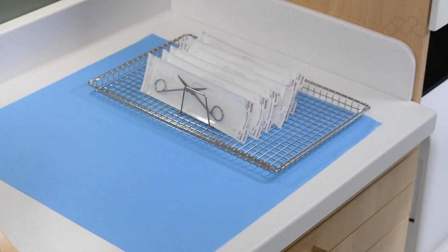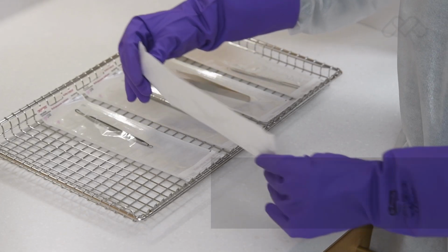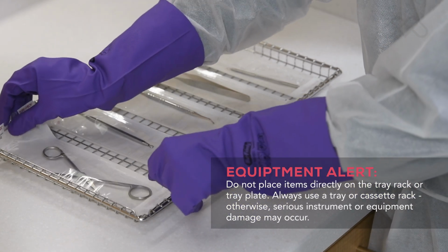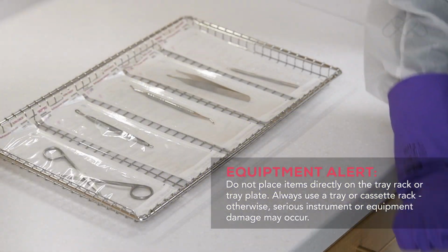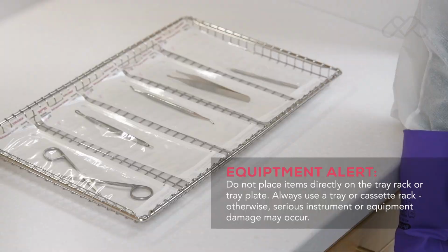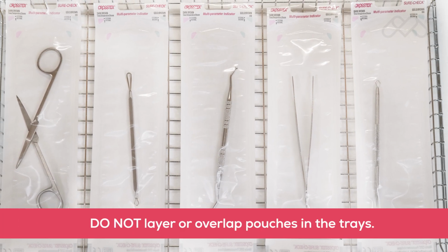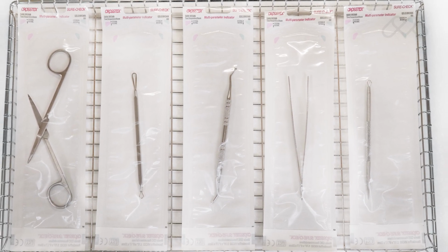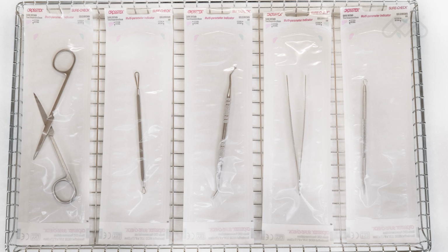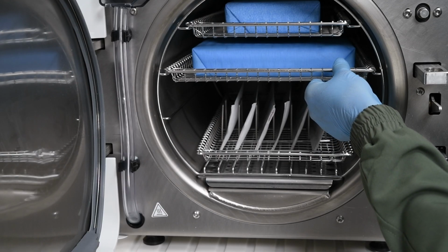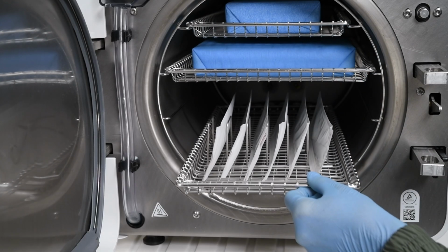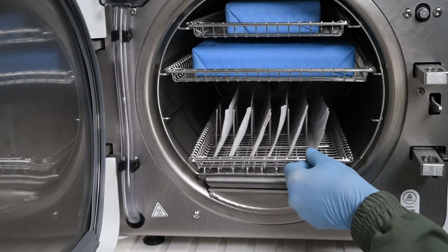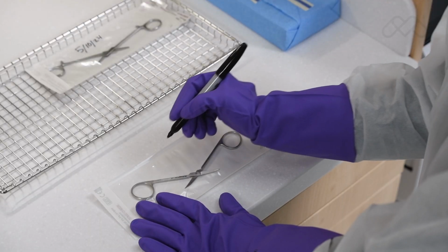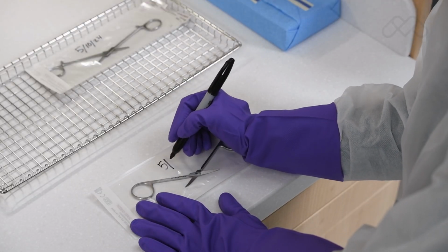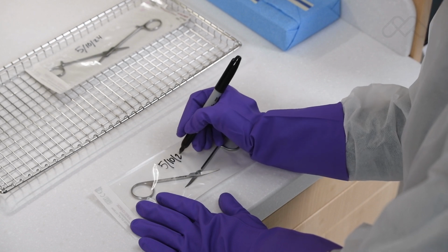Proper loading is using a pouch rack. Without a pouch rack, pouches loaded directly on the trays will dry best if loaded with the paper side down. Do not layer or overlap pouches in the trays. Pouches should be loosely packed with the handpieces and instruments, single height loaded to permit proper steam flow and penetration to the items. If pouches or wrapped packs are labeled using a marking pen, the ink should be non-toxic.